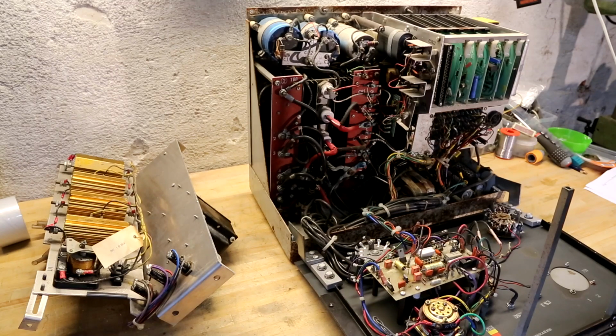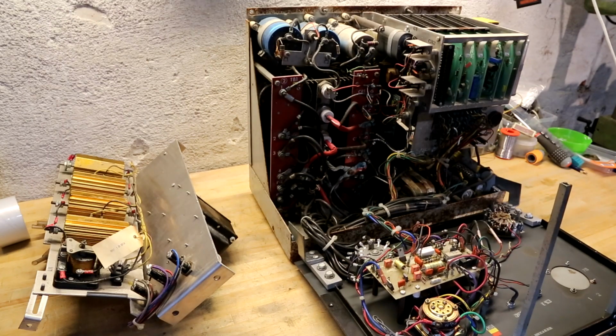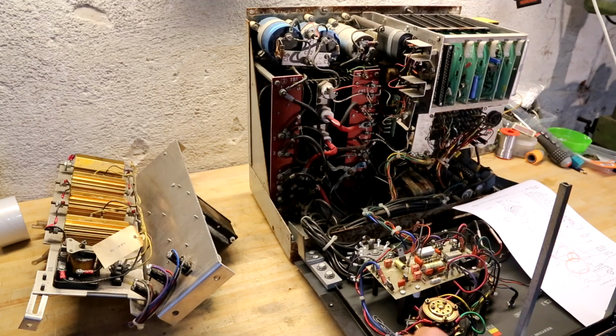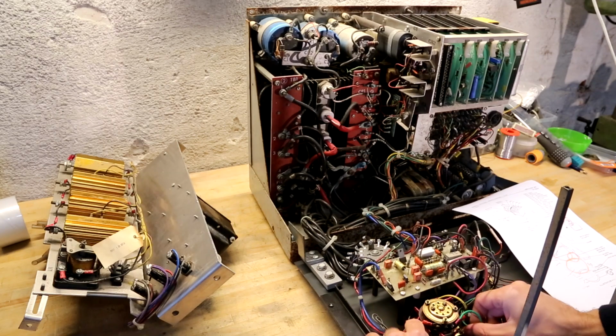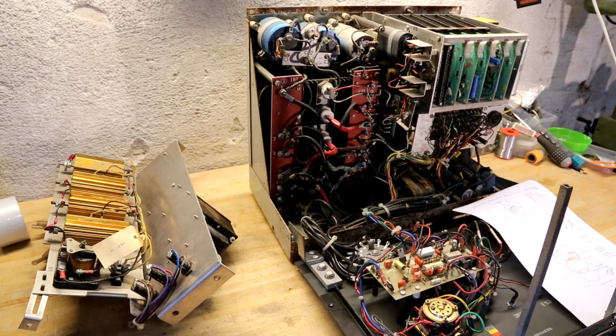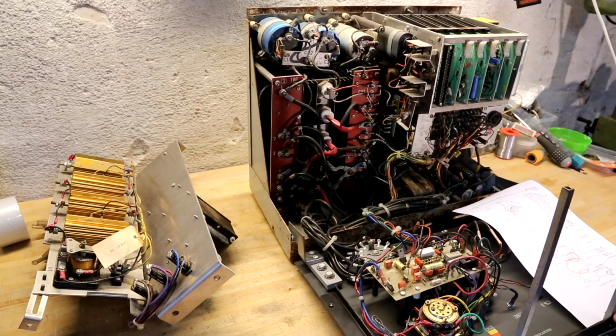So we're going to take the overview drawing and look at that once again. See, we have another warning down here. It says, warning, 118 volts present at all times. Remove fuses 6F1, 6F2 and turn circuit breaker 6CB1 to off to disconnect this voltage. So that is highly likely the connector to the battery bank.